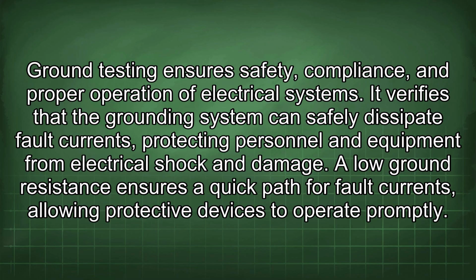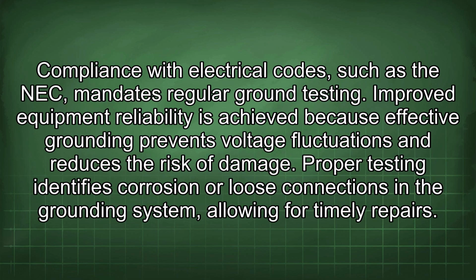Ground testing ensures safety, compliance, and proper operation of electrical systems. It verifies that the grounding system can safely dissipate fault currents, protecting personnel and equipment from electrical shock and damage. A low ground resistance ensures a quick path for fault currents, allowing protective devices to operate promptly. Compliance with electrical codes such as the NEC mandates regular ground testing.